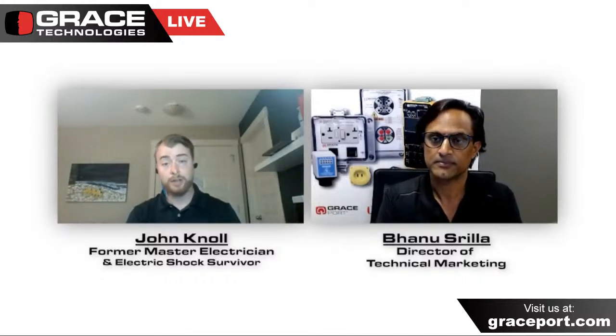The key takeaways I want to provide: work de-energized. Turn the breaker off, lockout, tag out. If you have to work energized, do it for testing purposes only, to verify things are working or to do your troubleshooting, and wear your rubber insulated gloves with leather protectors.